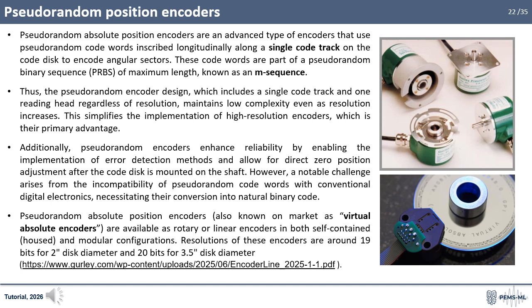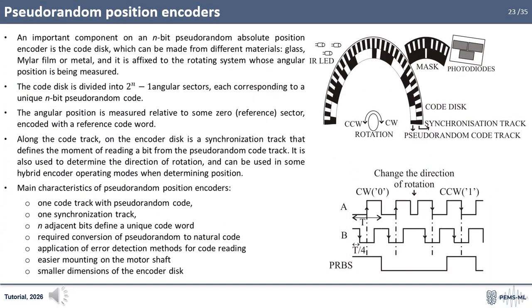Resolutions of these encoders are around 19 bits for 2 inches disk diameter and 20 bits for 3.5 inches disk diameter. An important component of an n-bit pseudorandom absolute position encoder is the code disk, which can be made from different materials, glass, mylar film, or metal, and it is affixed to the rotating system whose angular position is being measured. The code disk is divided into 2^n-1 angular sectors, each corresponding to a unique n-bit pseudorandom code. The angular position is measured relative to some 0 reference sector, encoded with a reference code word.